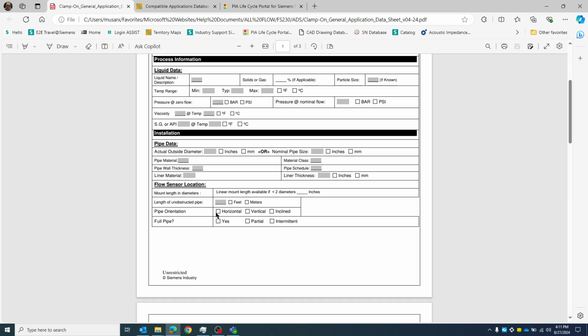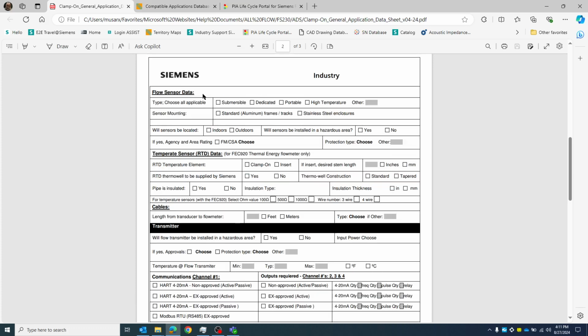What's the pipe orientation? Does it run horizontally, vertically, or inclined? If it's vertical, it would be a good idea to write down here if it's upward vertical or downward vertical, as downward vertical would oftentimes be problematic. We'd also like to know that this is a full pipe or a partially full pipe or something in between. As for the flow sensor data, we'd like to know if this is a submersible application.